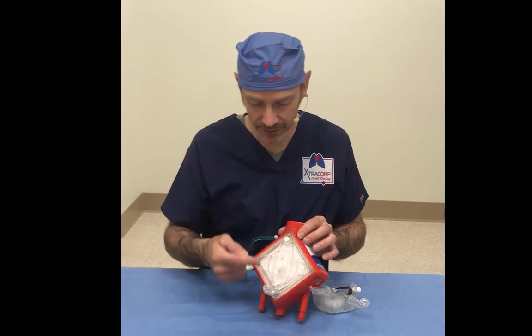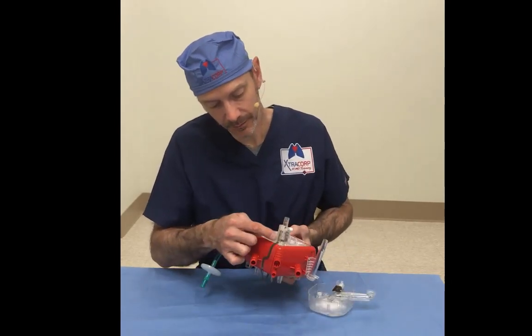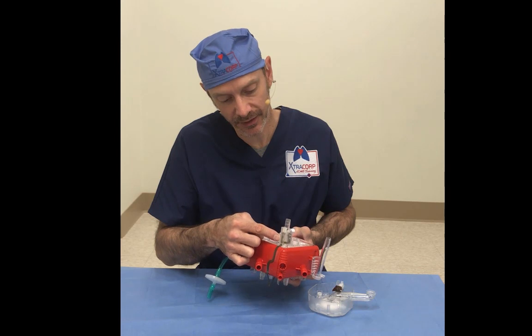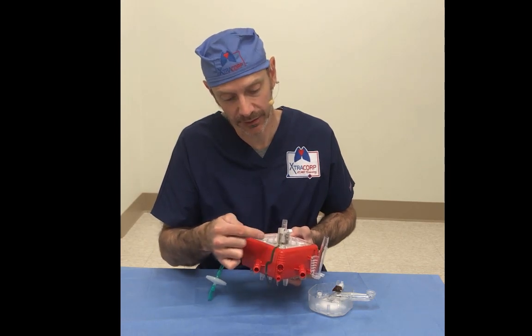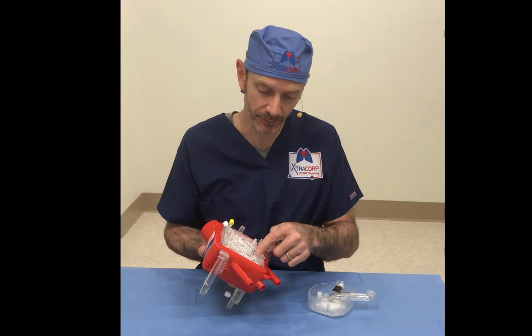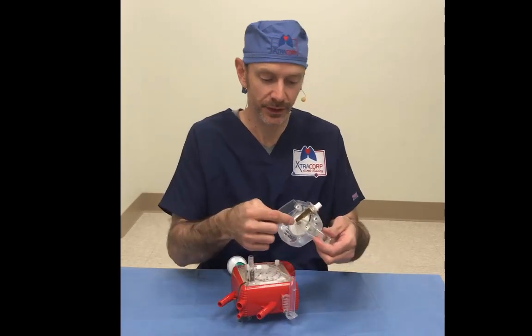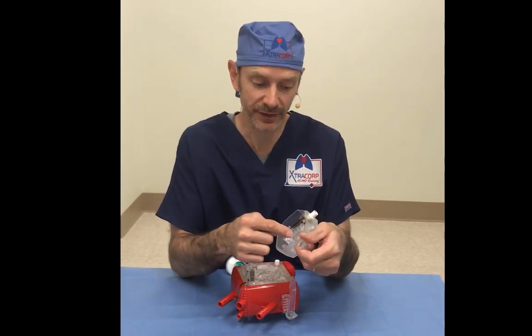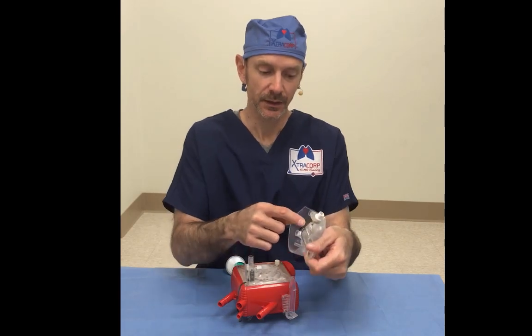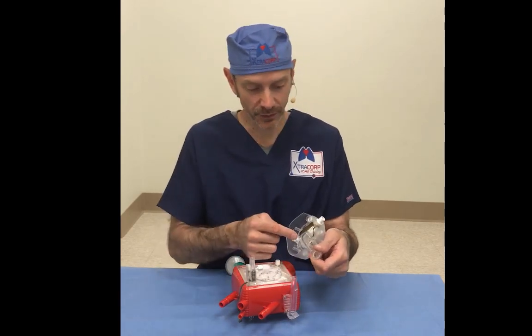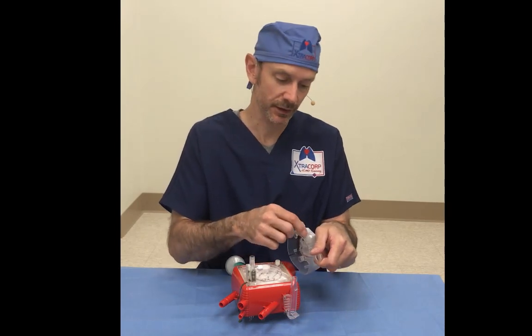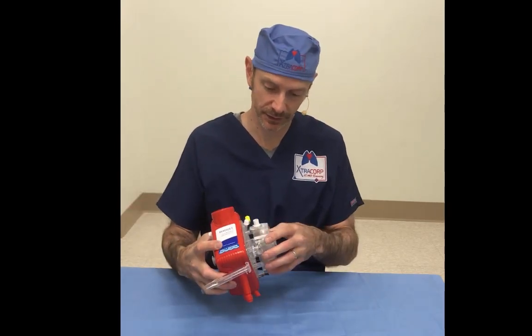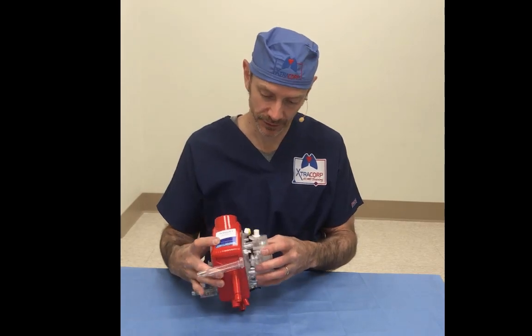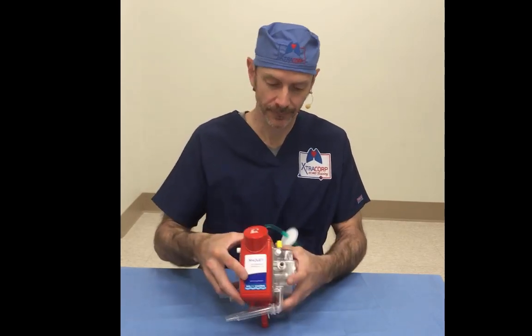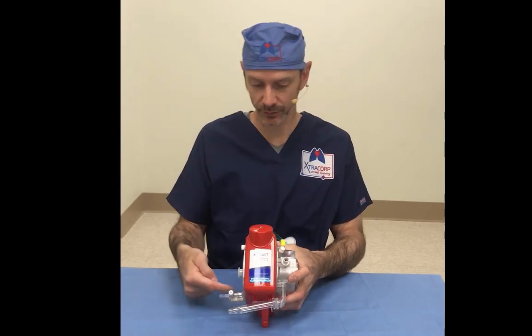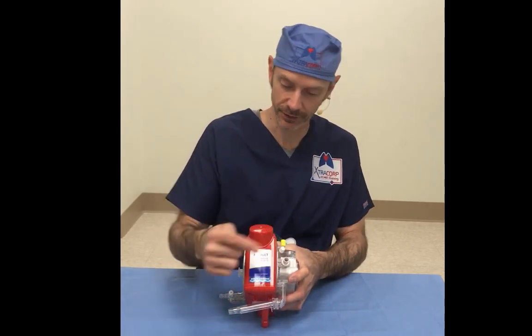And then when we get to the other side, there's another piece of electronic technology embedded right in the plastic here on the outlet. And this is the post-membrane temperature and pressure. Pre-membrane temperature and pressure. Pre-pump or venous line pressure there. And all 3 of those devices communicate to this electronic ribbon that comes up here and provides us access to the data. When this all snaps back together, we get our data from those 3 different sensors right here.